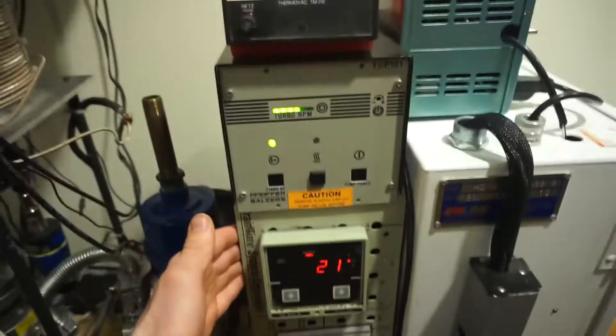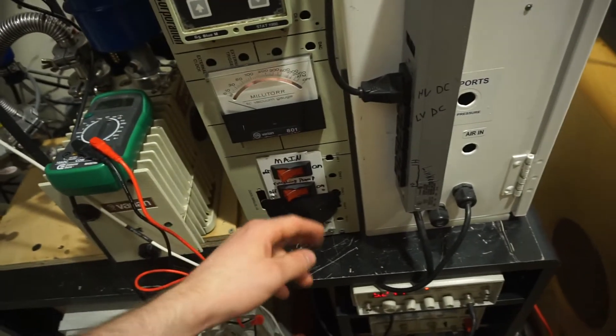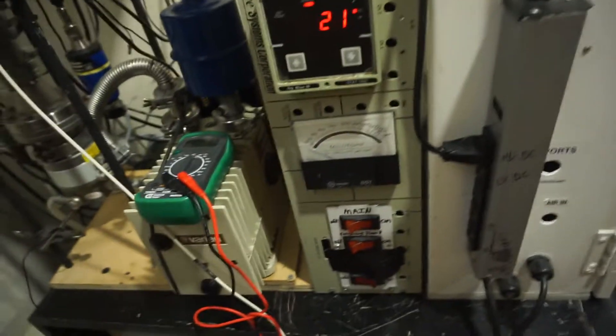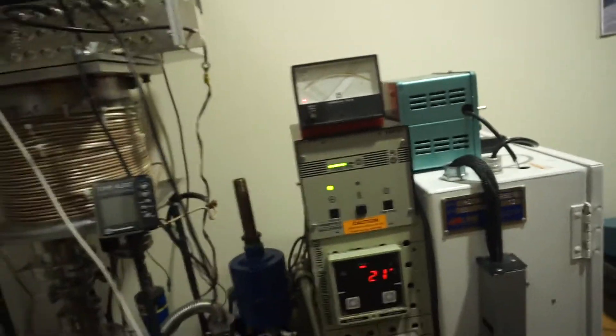So this is the control unit for the entire vacuum system. We have the turbo controller. We have main breaker switch, breaker switch for roughing pump, breaker switch for auxiliary heater, built-in thermocouple gauge, and then auxiliary thermocouple gauge.